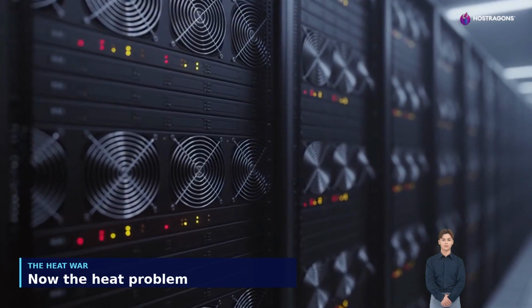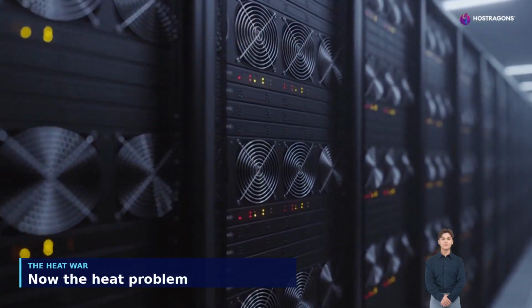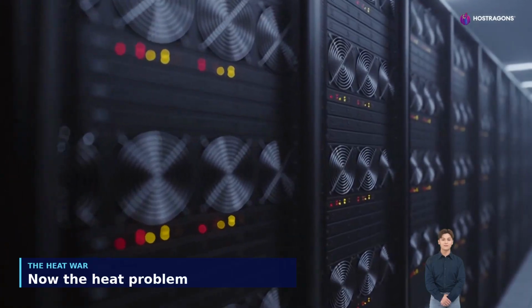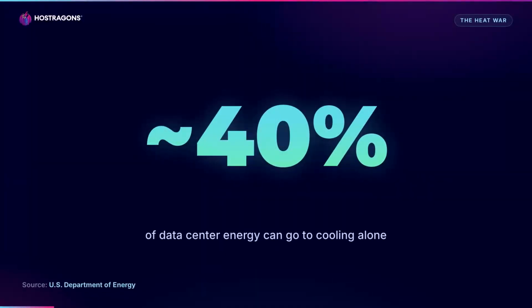Past the doors, the real work begins, and so does the heat. Every server is a tiny furnace, and there are thousands of them. A single high-density rack can burn through 30 to 50 kilowatts of power, as much as several homes, and nearly all of it turns into heat. Left alone, that heat would cook the electronics in minutes. Cooling can eat up to 40% of a data center's total energy just to keep things alive.